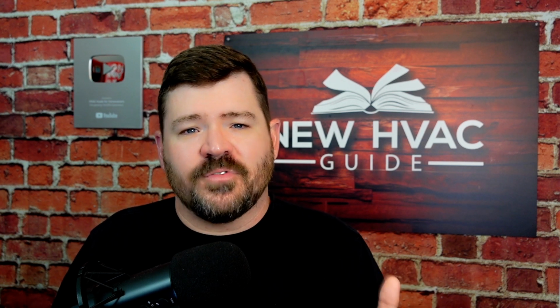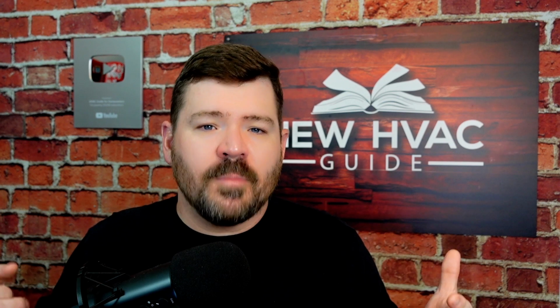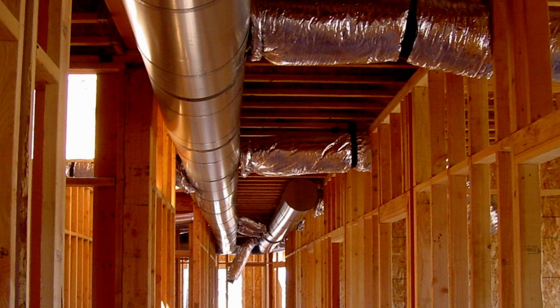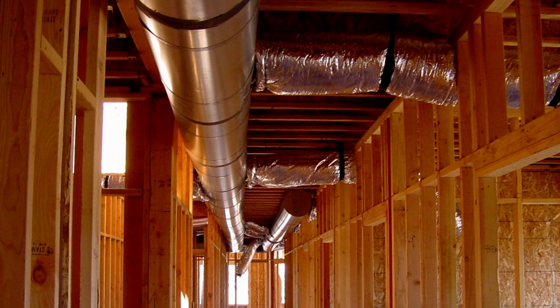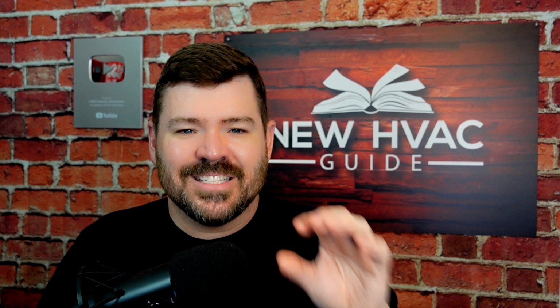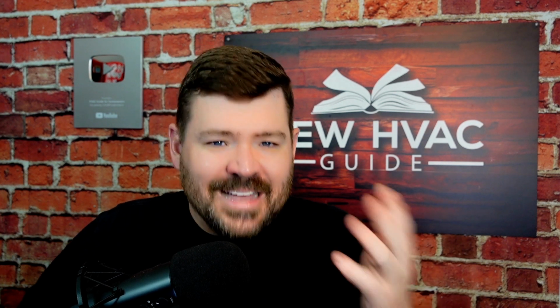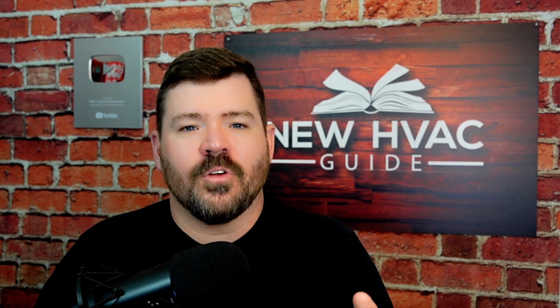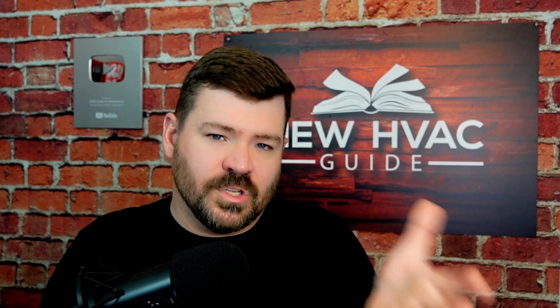I know this is a little more long-winded, a little more drawn out, maybe a little more in-depth than I normally get, especially when I'm talking to end consumers or homeowners, but it's a big problem that we're seeing in our industry. Ductwork has always been a problem. Ductwork has always been undersized, but I'm meeting contractors from time to time that don't even own a static meter. They don't own a manometer, whatever they need to use to test the static pressures. They don't own anything. And that's a huge problem, especially if they are the ones that are speccing these jobs, selling you the systems. They need to have the tools to do the job correctly.